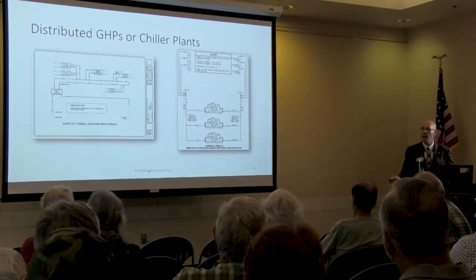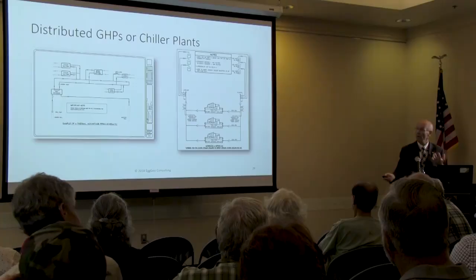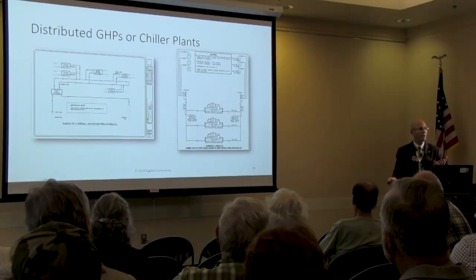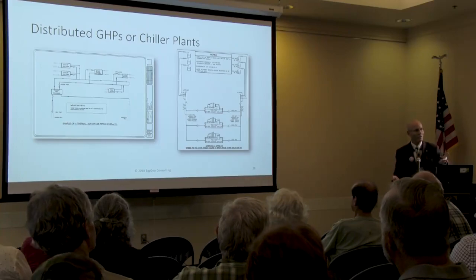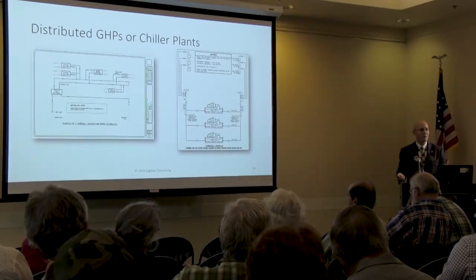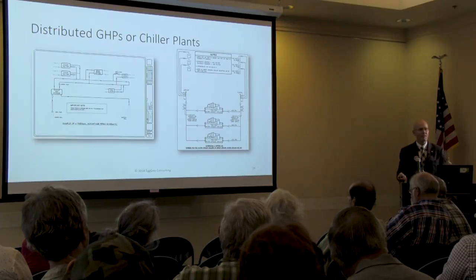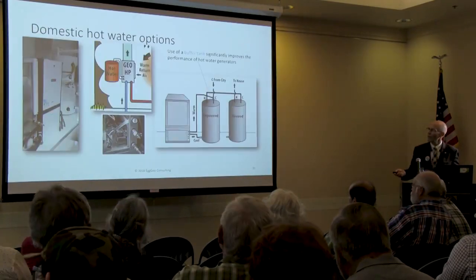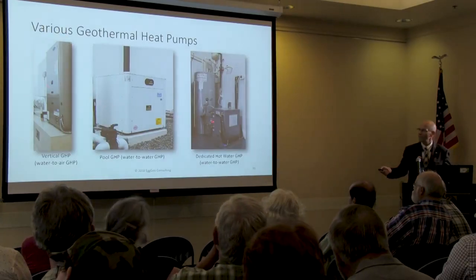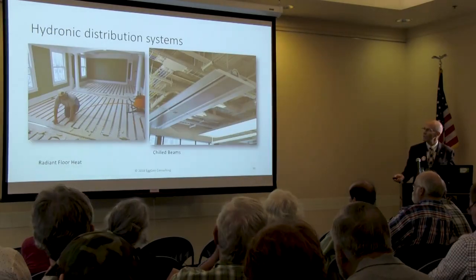So some, like the dedicated domestic hot water heat pump, are pulling heat from the loop because they're making heat for the hot water tank, while those that are cooling the building are rejecting heat to the loop. And if you think about it, you can't do this with air source heat pump equipment, and certainly you can't do it when you're burning fossil fuels. What a waste of resources. When you're doing a water source heat pump, you can share these BTUs, and that is the essence of sustainability. So these can live in harmony on a condenser water loop in a building.